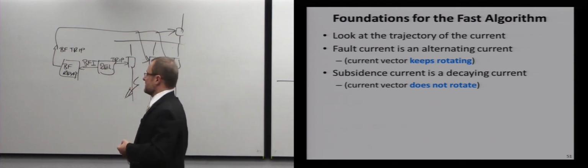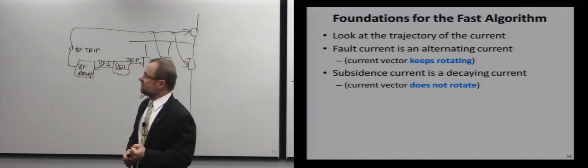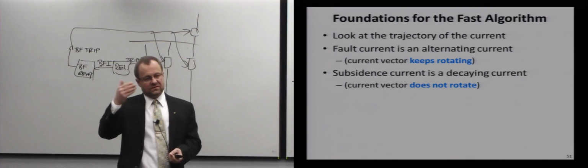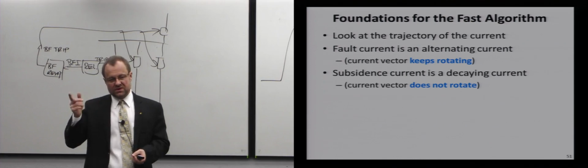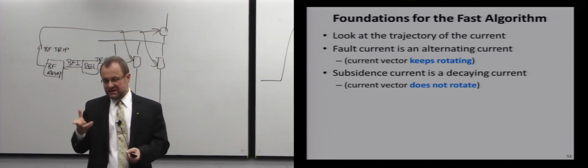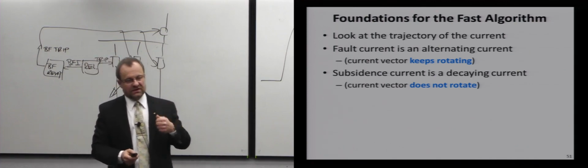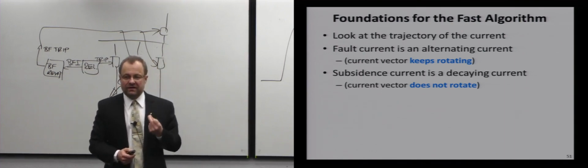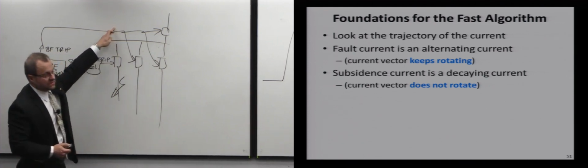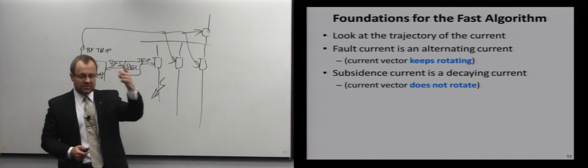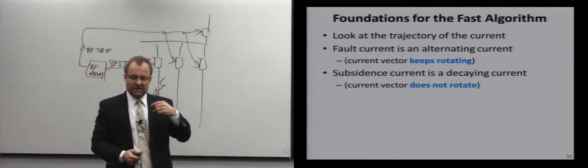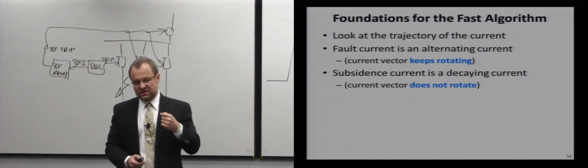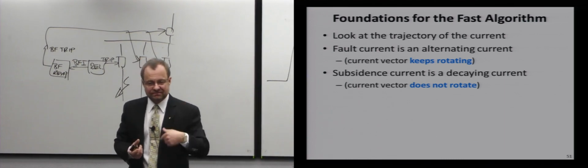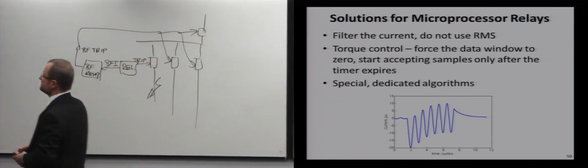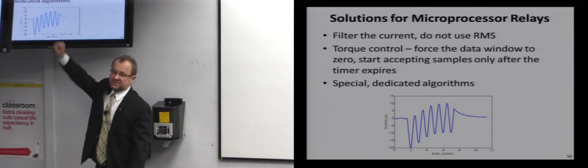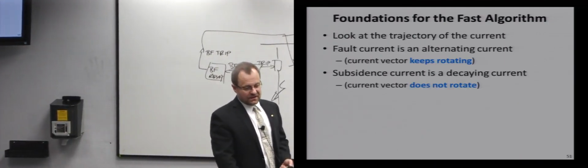Let's look at the trajectory of the current. And what does it mean, trajectory? I could take the current and look at the derivative of the current. And when I plot those two things on a two-dimensional plane, I will make circles, right? AC is a rotating vector, so to speak. So I could go to this rotating picture, and what's the difference? If I have a fault current, that means that there is an AC source that drives that fault current, meaning that I keep rotating. I may be heavily distorted by the DC component or CT saturation, but the prevailing motion that I'm going to see is rotation. When I get to this point here, the current is not zero, could be far from zero, but it stops rotating, right? So how could I do that?